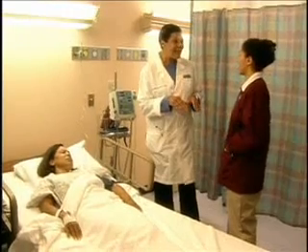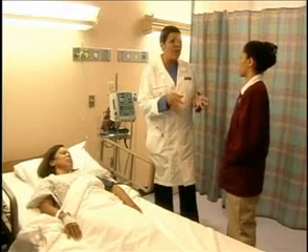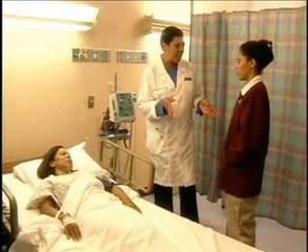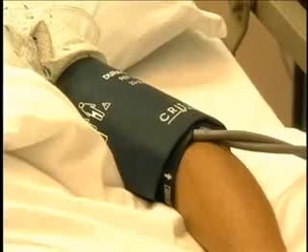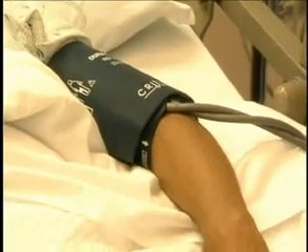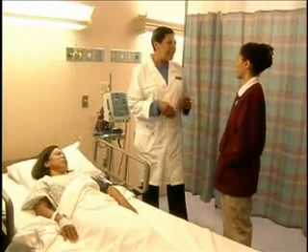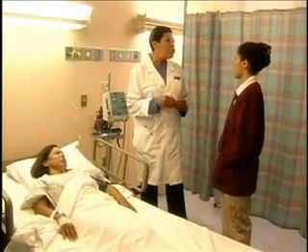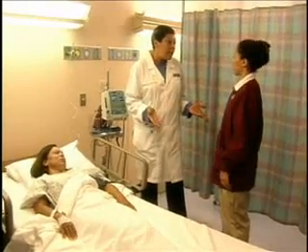Yes, it is. See, when using something like this, you have to keep in mind that irregular heart rates, room noise, or even excessive movement of the patient can interfere with the readings. And you also need to make sure that the cuff is completely deflated after the readings. Now, why is that? Because if it doesn't deflate all the way, it can cause inadequate arterial perfusion and venous drainage, which can compromise circulation in the limb.